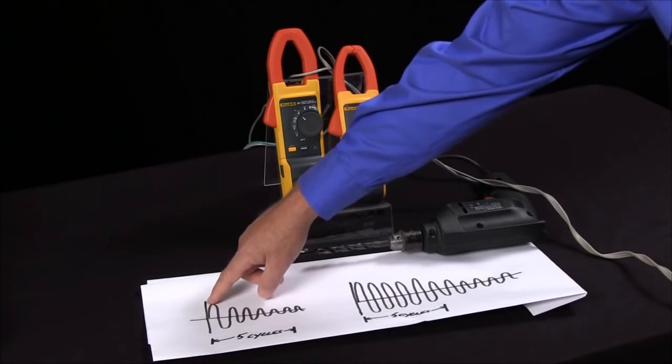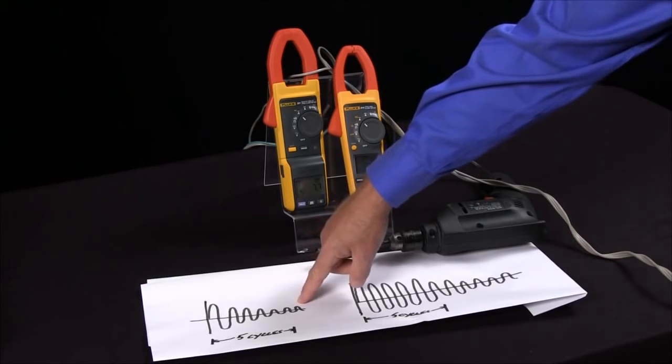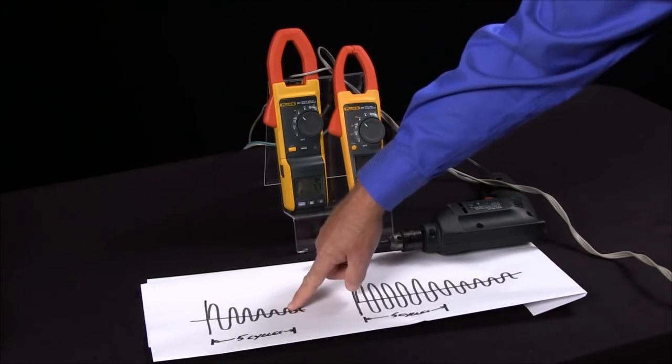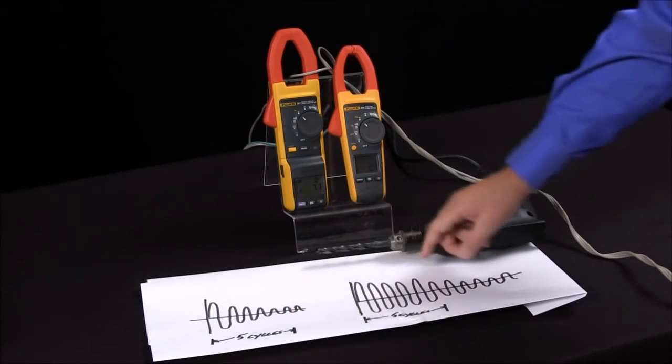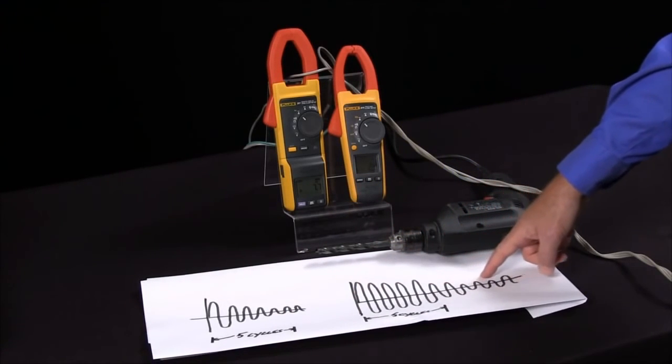And not only is the amplitude important but also how long it takes to settle out. With a good inrush current it settles out very quickly with a good motor. If we have a bad or aging device it may take quite a long time to settle out.